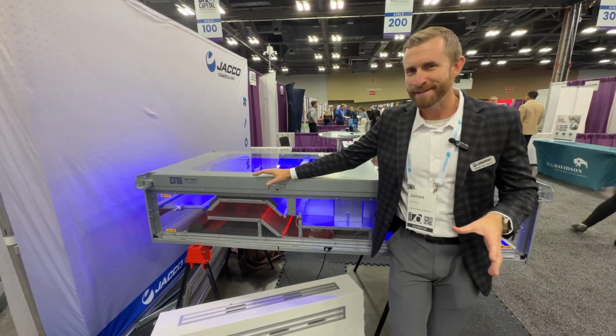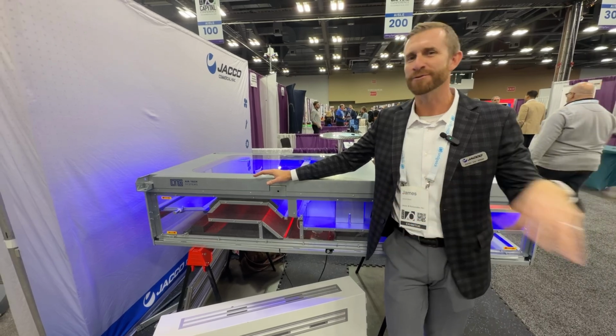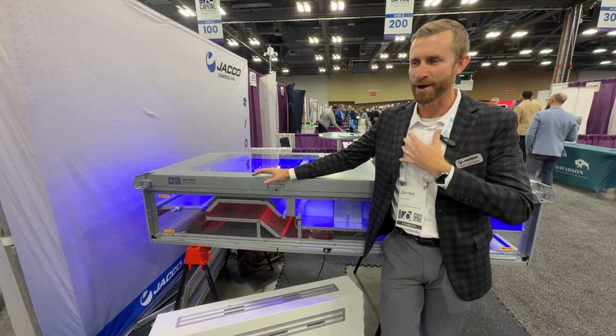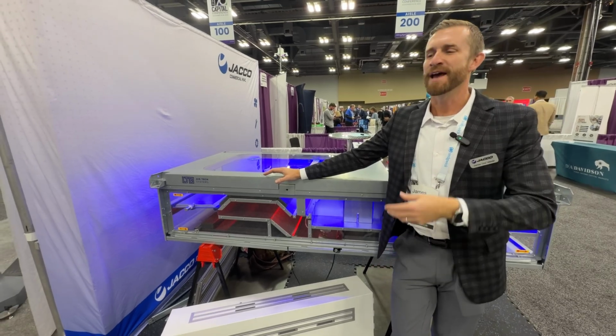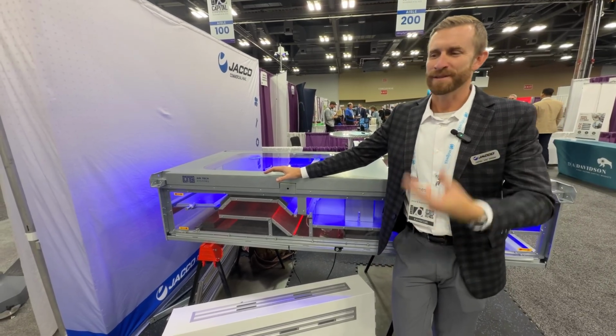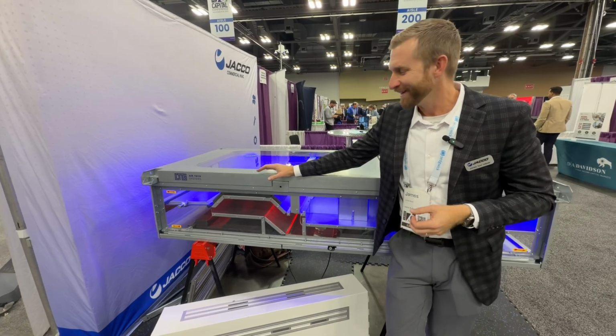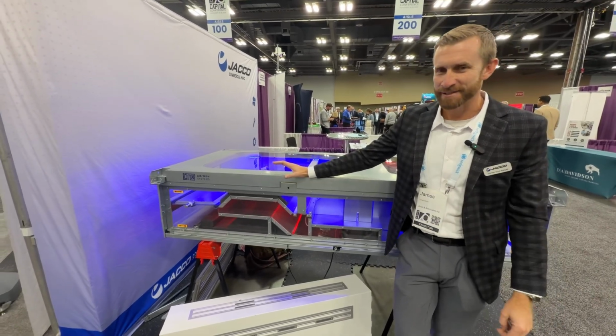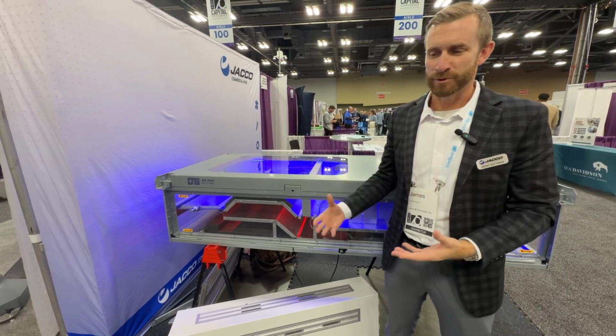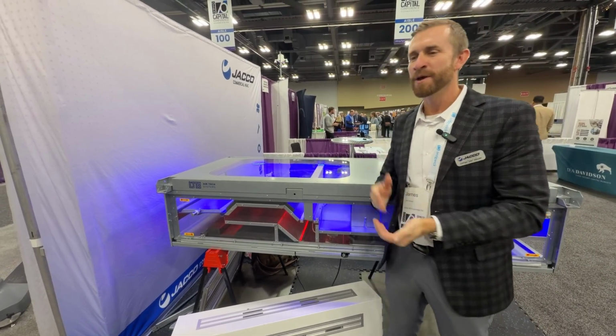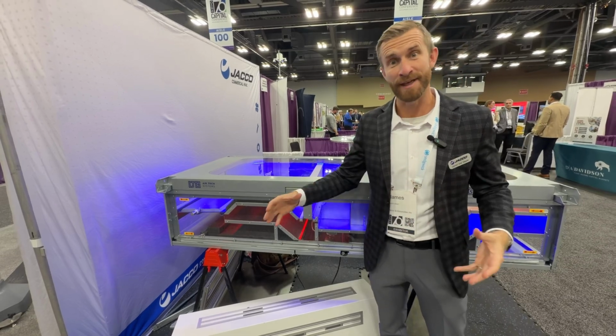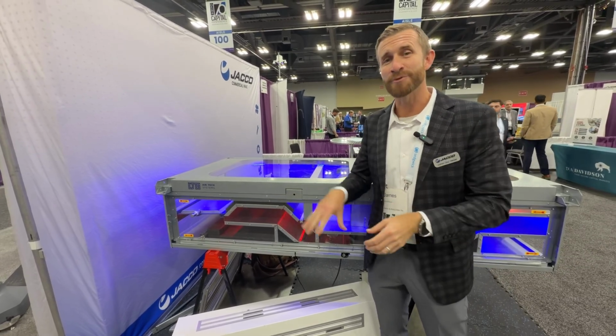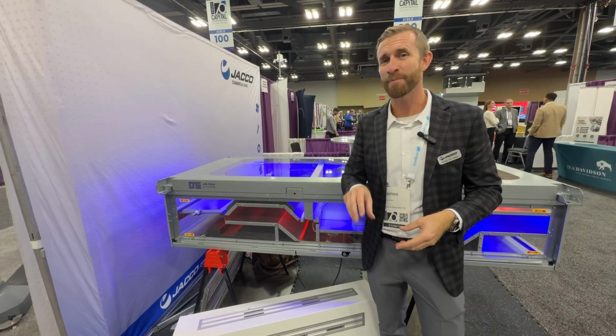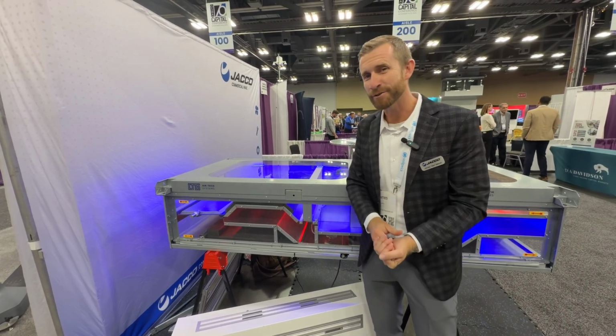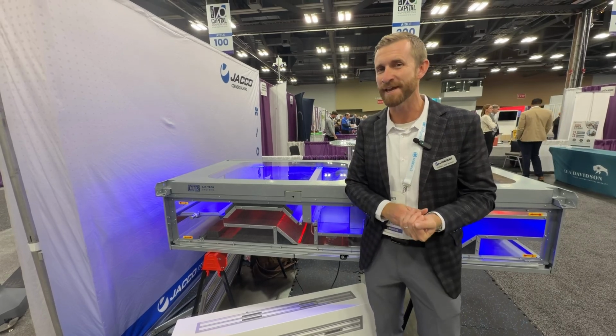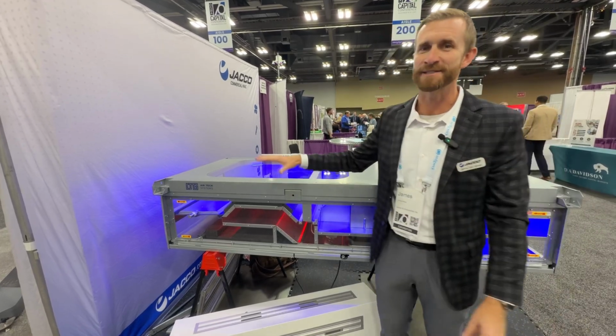So you have 30 kids in a classroom, and all of them are breathing each other's air. We were all sharing the air. Every time you take a breath and exhale, CO2 is coming out, and it's filling the space with basically things you don't want to breathe, right? ASHRAE in the United States has said that for every school building, say it's a 500 square foot classroom, 0.12 CFM of outdoor air needs to come into that 500 feet. In addition, every student in that room needs 10 CFM of outdoor air per student. So if you have 30 kids in a 500 square foot classroom, you need 360 CFM of outdoor air to come into that space to meet building code.